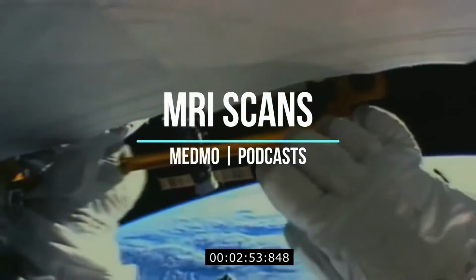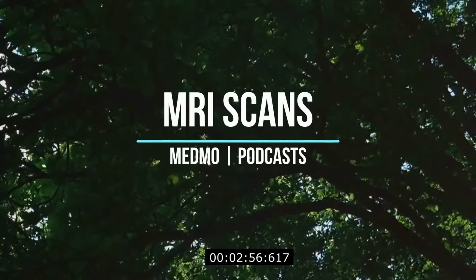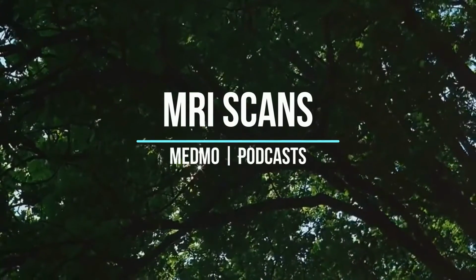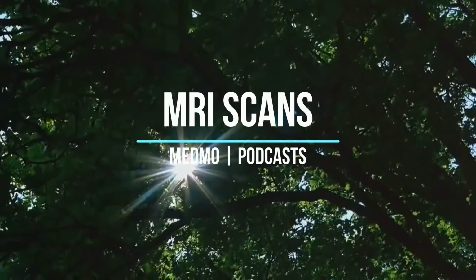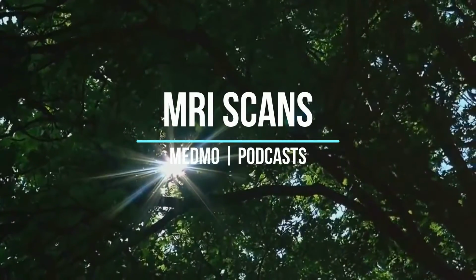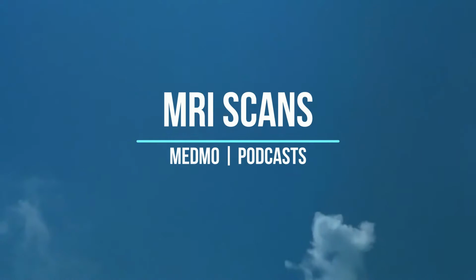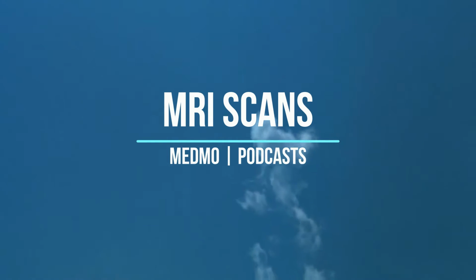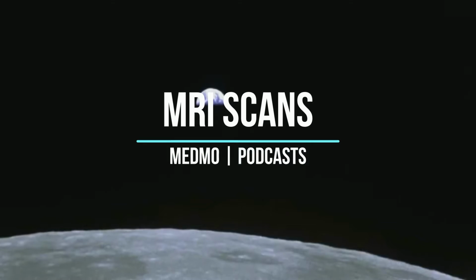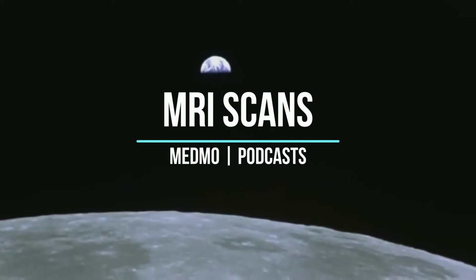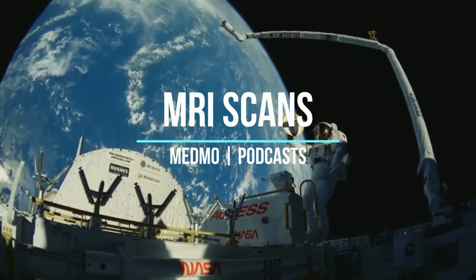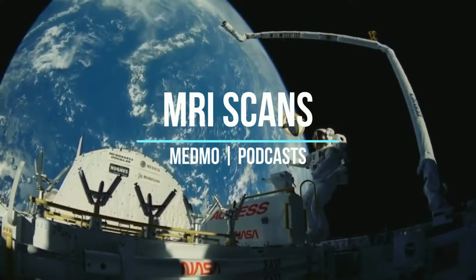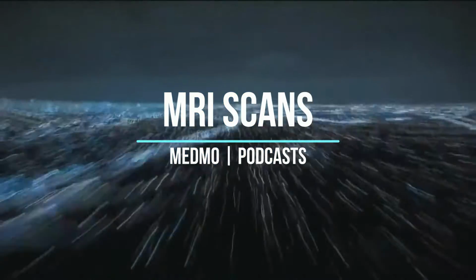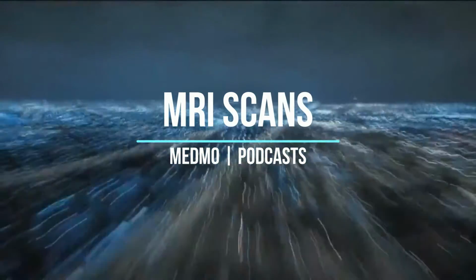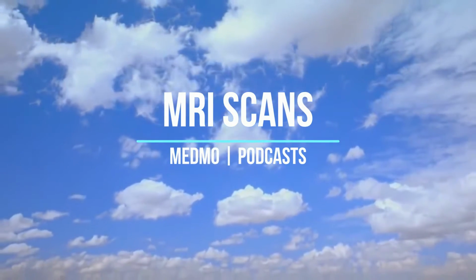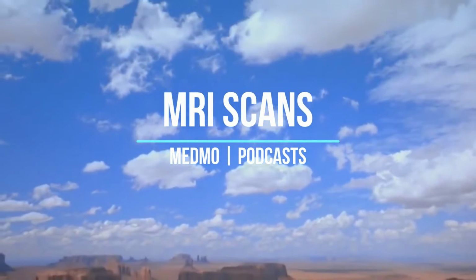Now, most MRI systems use an electromagnet, as you may remember from GCSE as well. Electromagnets are made from coils or windings of a wire, and a current is passed through. Now, to create such a huge magnetic field, up to 2 to 3 Teslas, we're going to need a huge deal of energy, especially to maintain such a magnetic field. And to lower the cost, you may remember, especially A-level students, something to do with superconductivity, reducing the resistance, and ensuring that we can maximise the biggest field we can get out by lowering the cost and lowering the use of energy. And we do this by cooling the wire down using liquid helium.